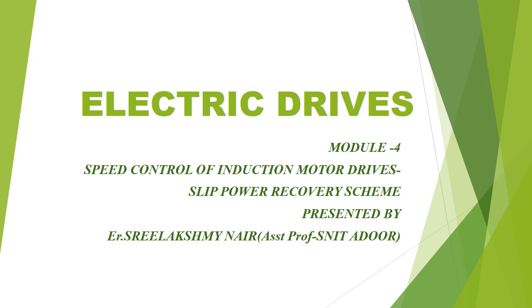This slip power recovery method is the most prevalent and best method to date to control the speed of an induction motor drive, because other methods suffer from many limitations such as significant power loss, generation of noise and harmonics on the supply network, lower power factor, and low efficiency. The slip power recovery scheme is used for limited speed range operation of induction motor drive, where slip power is a fraction of motor power rating, therefore requiring low power rating converters and lower cost.